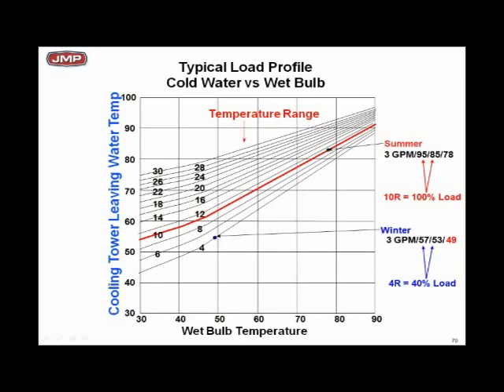So what are you learning? Cold air holds less moisture. As I slide the wet bulb down, the approach on a cooling tower, anybody's cooling tower, has to go up dramatically at the same range, at the same load. Please hang on to those statements because it impacts your waterside economizer sizing immensely.